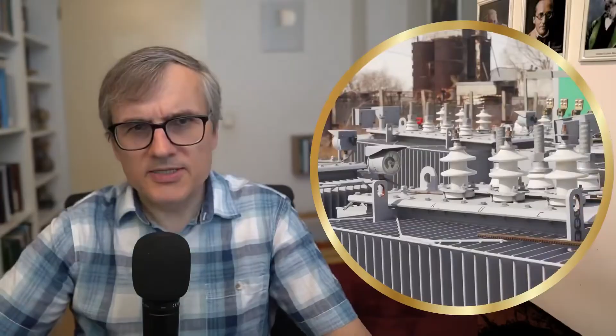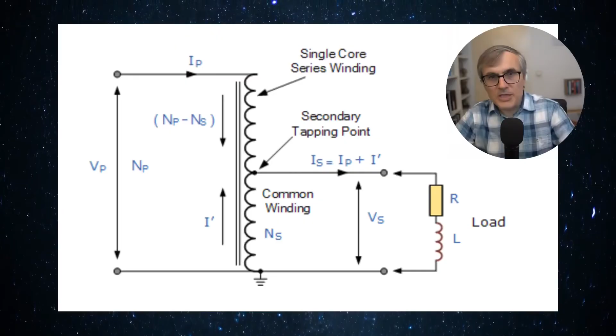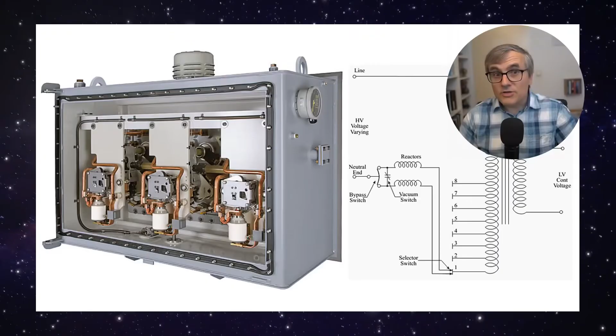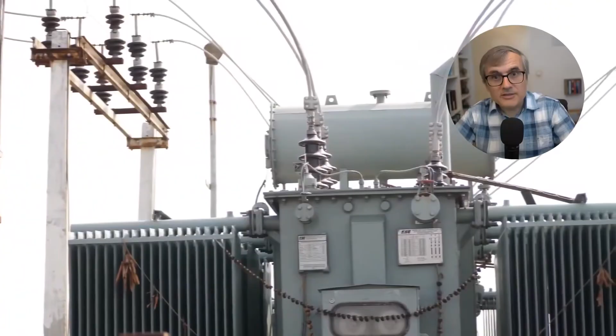volts. In transformers with variable electric voltage, this low voltage delivered to consumers can be automatically adjusted, depending on the user's load. If they consume a lot, the electric voltage naturally drops, and then the transformer will raise its secondary voltage. The same thing happens when the consumption decreases. The voltage would naturally increase. The variable voltage transformer measures this and delivers a lower voltage on the secondary side. Such a solution also benefits prosumers. A sunny day arrives and all the prosumers on the line deliver energy. Voltage in the networks rises, and the transformer sees this. Being variable, it will automatically lower its voltage.